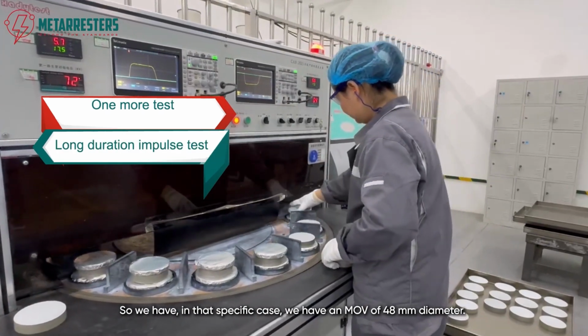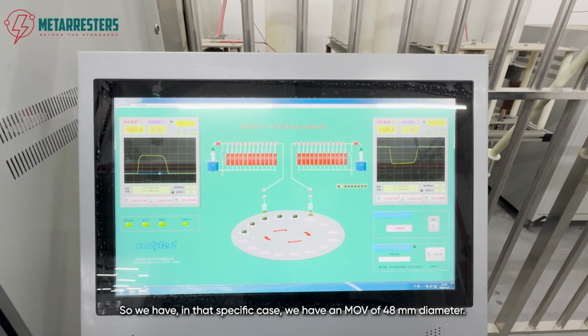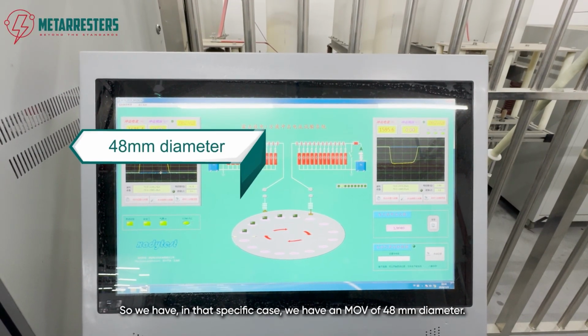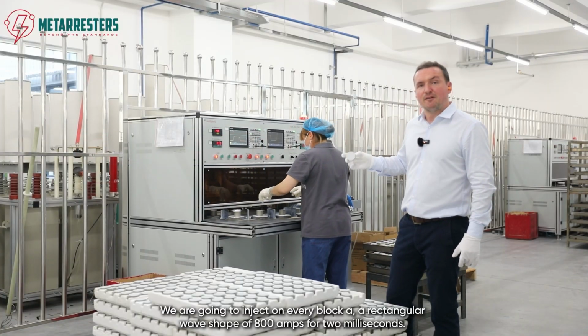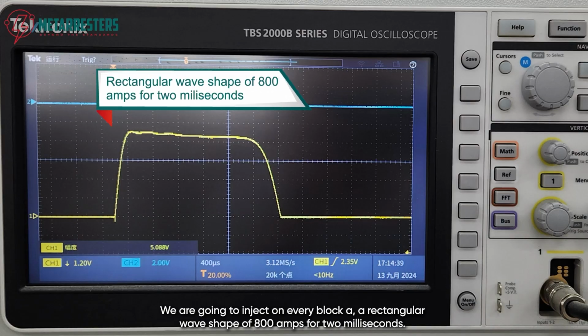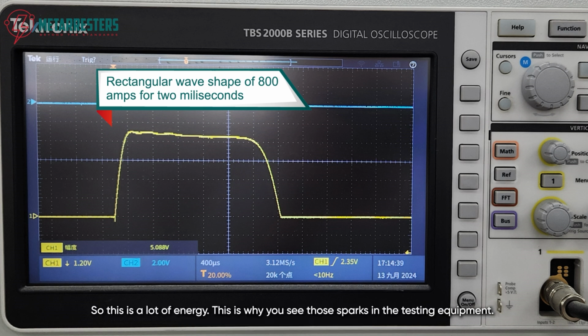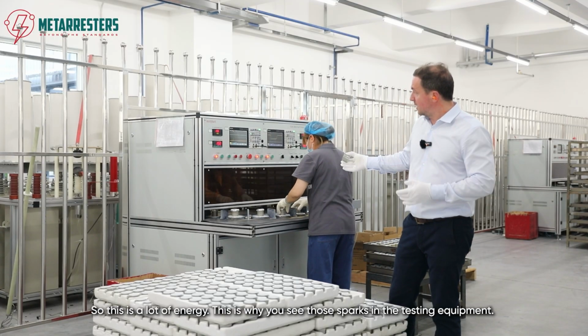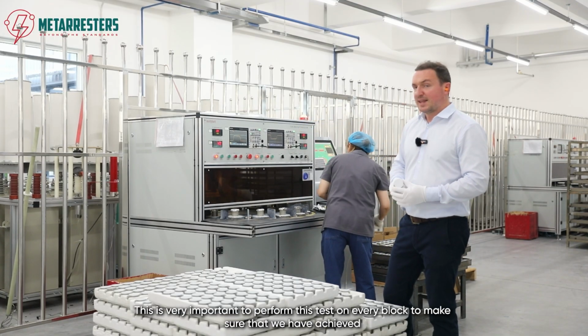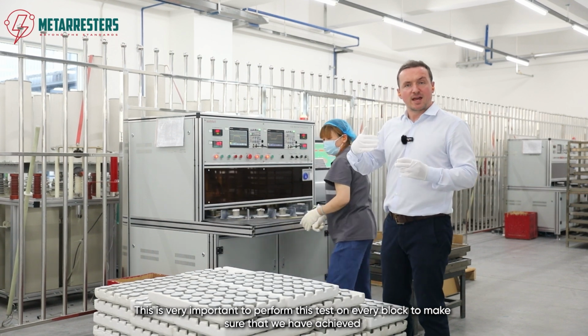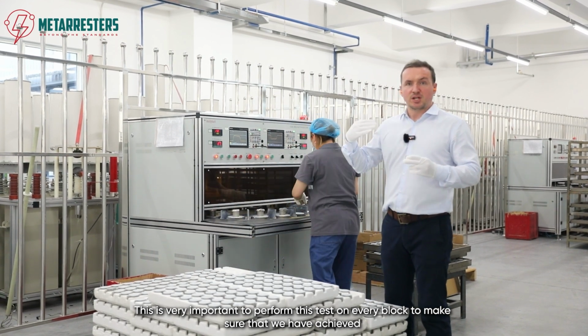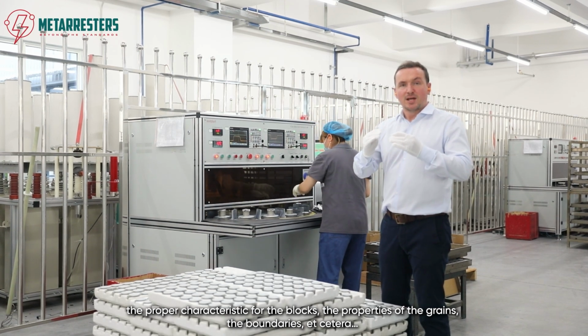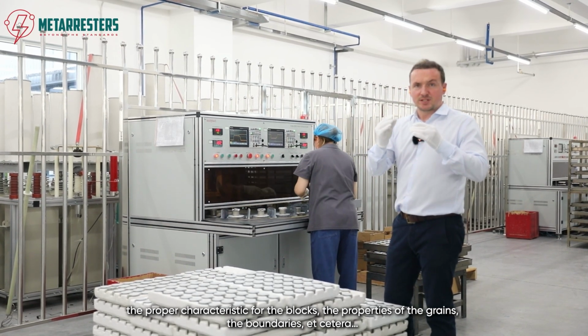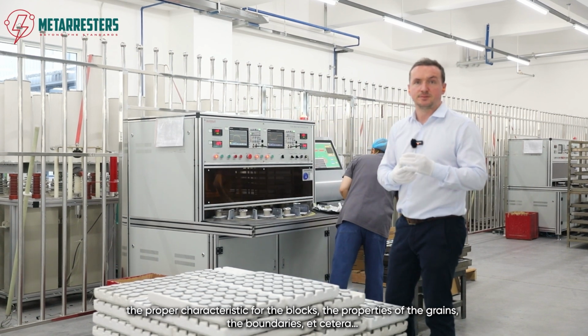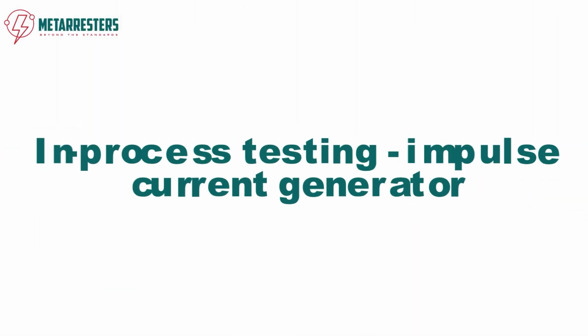In that specific case, we have an MOV of 48 millimeter diameter. We are going to inject on every block a rectangular wave shape of 800 amps for 2 milliseconds. So this is a lot of energy. This is why you see those sparks in the testing equipment. This is very important to perform on every block to make sure that we have achieved the proper characteristic for the block, the properties of the grains, the boundaries, etc.